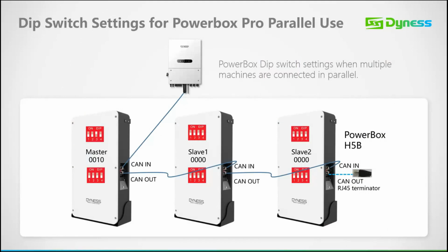When using more than one Powerbox Pro in parallel, our Powerbox Pros come preset from the factory, having a master set to 0, 0, 1, 0. When connecting more than one Powerbox Pro, your slave Powerbox Pros need to be opened and the slave switches need to be adjusted accordingly. So for slave 1, it is 0, 0, 0, 0. For slave 2, you repeat the same dip switch setting up until 5 Powerbox Pros in parallel.